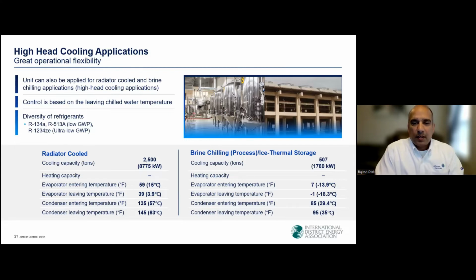So we have air-cooled condensers, or sometimes referred to as radiators, to cool the condenser water that is flowing through the units. Because it's air-cooled, the entering condenser water temperature to the unit is very elevated, such as 135 F or 57 Celsius, as you can see on the slide. Thanks to the compounding technology, the unit is able to deliver as low as 39 Fahrenheit or 4 Celsius, which is used for comfort cooling. The second example is of brine chilling, where the unit is producing as low as -1 Fahrenheit or -18 Celsius for process cooling.